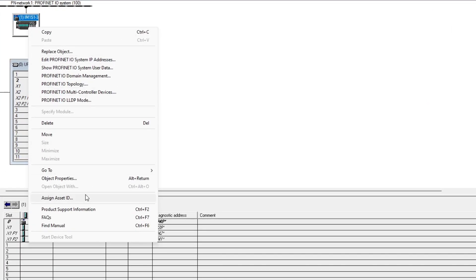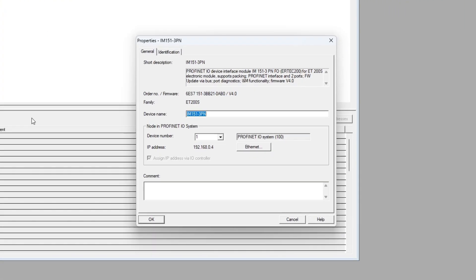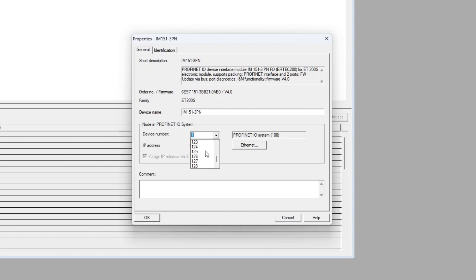If we right-click our I.O. device and then click on object properties, we will get a menu to do some settings. We can give our device a number. We can have up to 128 devices in a Profinet network. I will keep this one as number 1 and name it device 1.